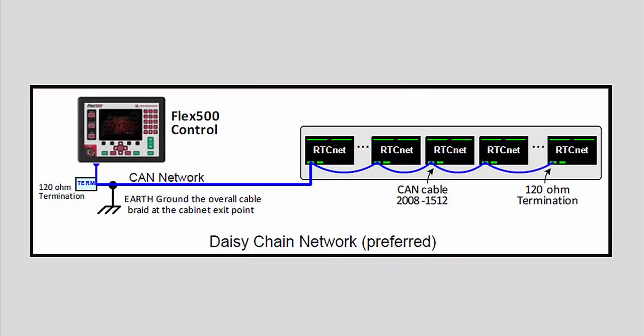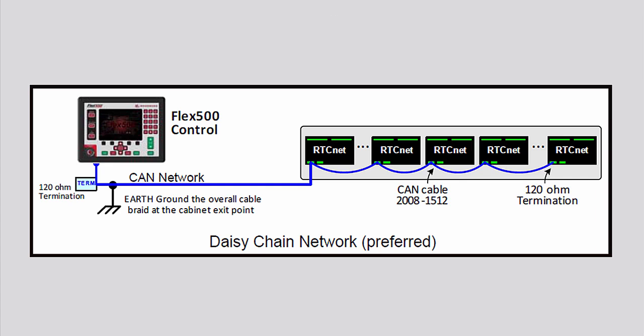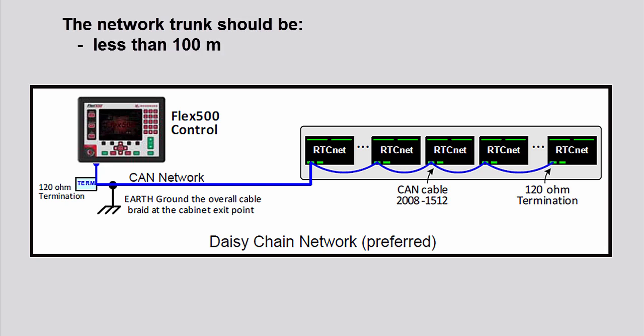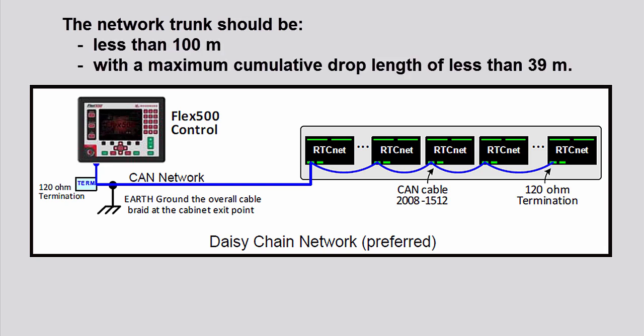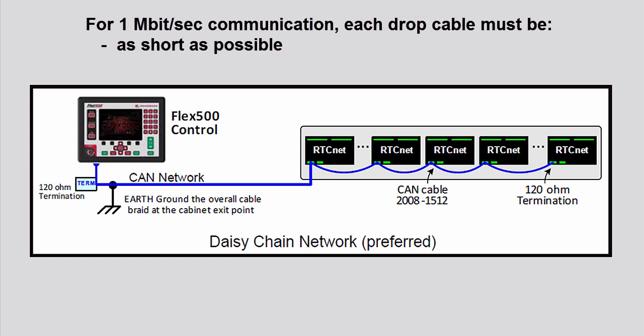If multiple connections need to be made, Woodward recommends daisy chain connections. Any drop cable connection of a device to the trunk line should be as short as possible and much less than 6 meters. It is recommended to design the network trunk to be less than 100 meters with a maximum cumulative drop length of less than 39 meters. For 1 megabit per second communication, each drop cable must be as short as possible and definitely less than 1 meter.